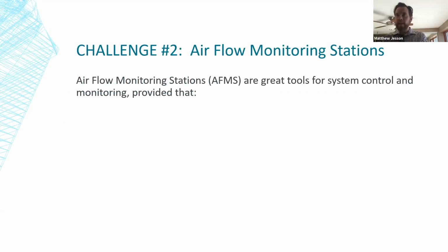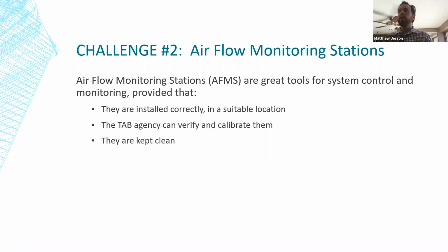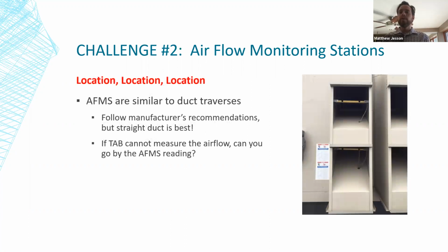I should say that airflow stations themselves are not the problem. They're great tools for getting your system under control and doing monitoring, but you just have to keep in mind the limitations as usual. They have to be installed correctly in a suitable location. The TAB agency needs to be able to verify and calibrate them, and they need to be kept clean. It's all about location, of course.